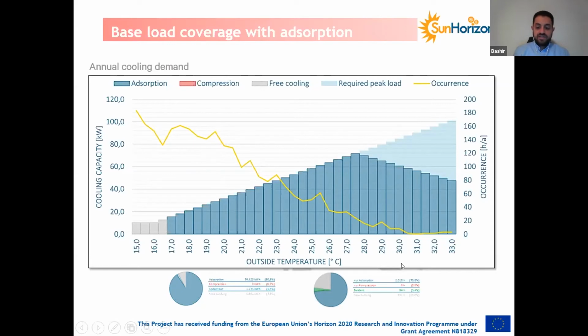And of course, the higher temperatures occur only for a few hours per year, which is why we recommend that adsorption is designed for base load coverage. So we recommend covering the hours where we have lots of cooling demand with adsorption, and then we will have some peak load that requires covering only for a few hours, and this is where we need a backup system. Now, this helps with the reliability of the overall system and also helps with the limitation of the heat, because it can be that the available heat is not enough to cover the whole cooling load.